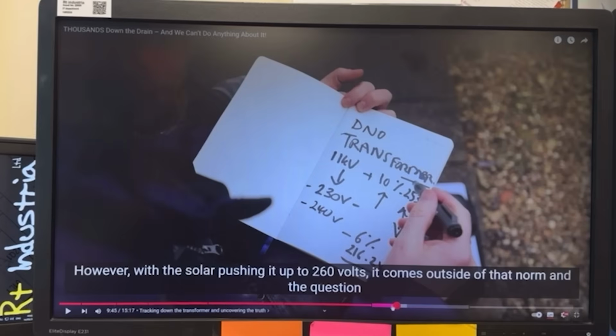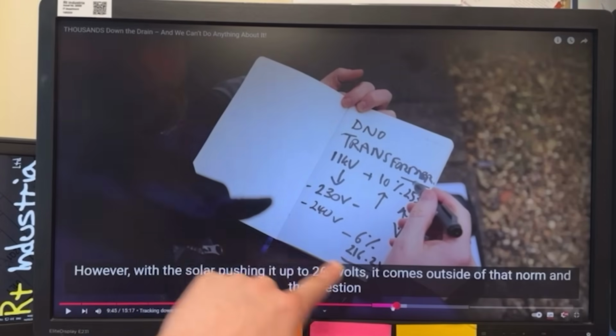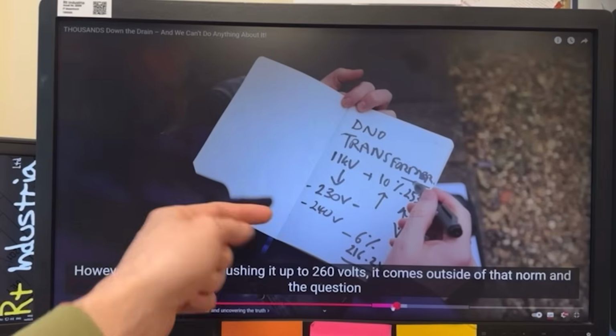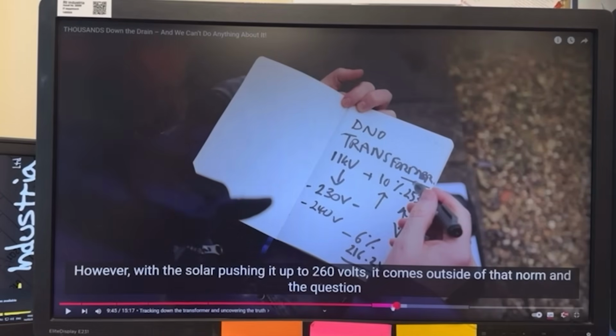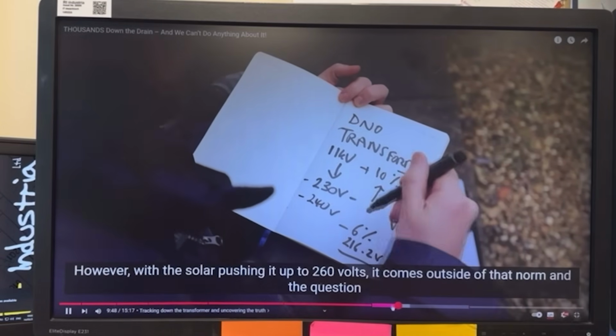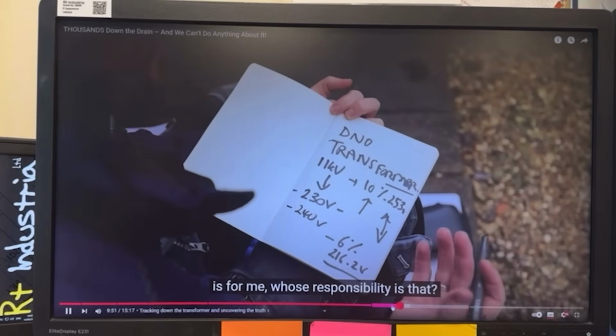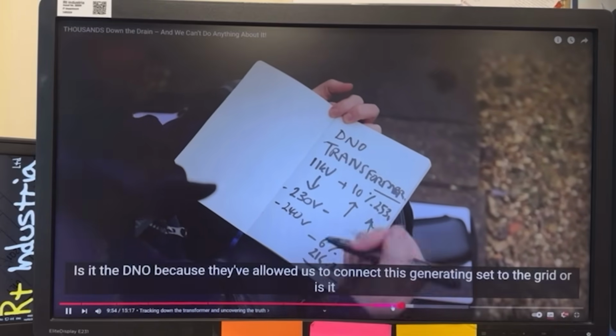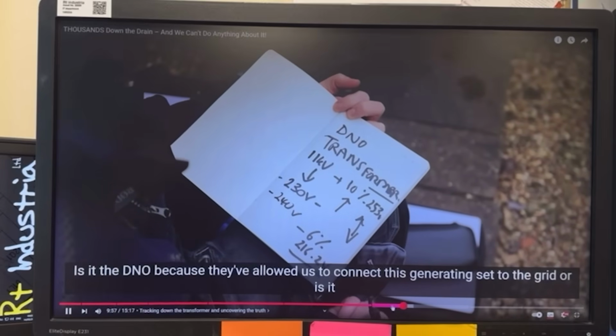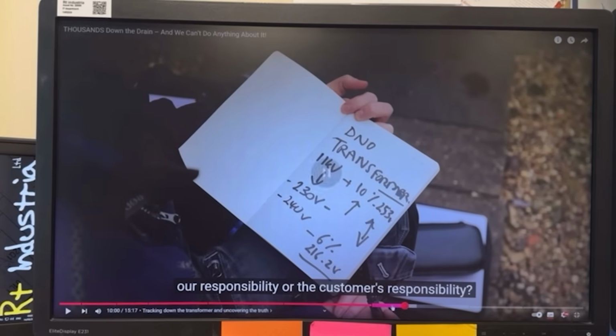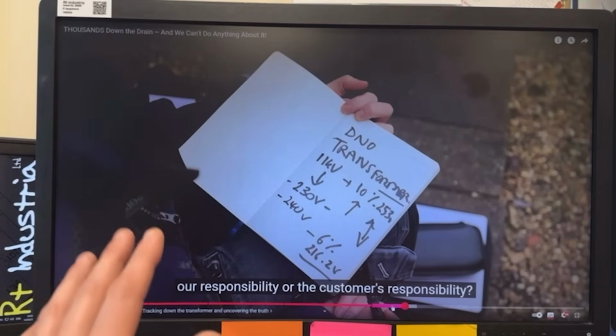You're admitting your solar's pushing up to 260 volts, which is outside the specifications you just outlined, not just for them to send to you but for you to send to them. That's outside the norm. The question is, whose responsibility is that - the DNO, because they've allowed us to connect this generating set to the grid, or ours? I'd argue it's a bit of both. It is a bit of both, but when they allowed you to export 17 kilowatts, I doubt they expect you to be pumping it out day in, day out. However, they should probably think about that, because we've got to remember, as well as Jordan and people like him being on a learning curve, so are the DNOs.